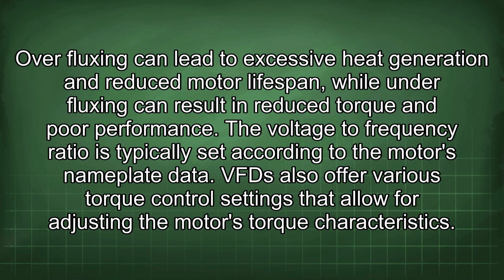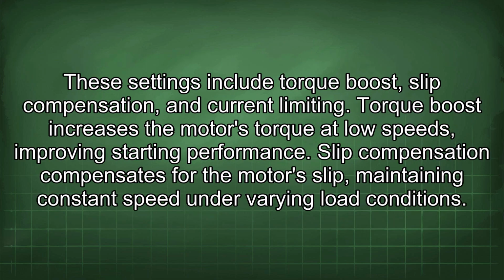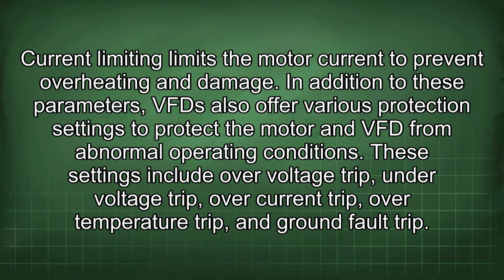VFD also offer various torque control settings that allow for adjusting the motor's torque characteristics. These settings include torque boost, slip compensation, and current limiting. Torque boost increases the motor's torque at low speeds, improving starting performance. Slip compensation compensates for the motor's slip, maintaining constant speed under varying load conditions. Current limiting limits the motor current to prevent overheating and damage.